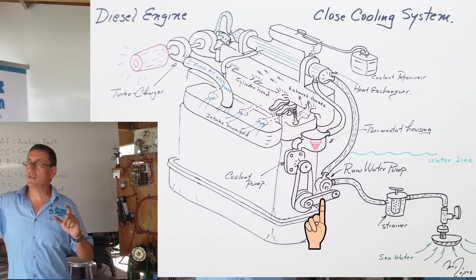When you have a temperature problem in a diesel engine, gas engine, or marine engine, you need to isolate the problem. You need to isolate whether the problem is on the coolant system or on the salt water system. If the problem is on the salt water system, you need to verify from the sea cock, from the valve, from the strainer, and the raw water pump, and verify if the raw water is passing all of these parts and entering the heat exchanger.